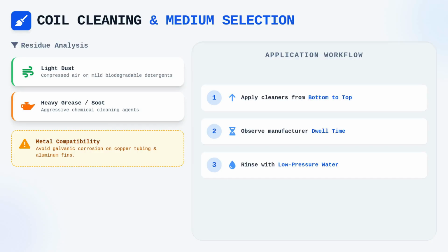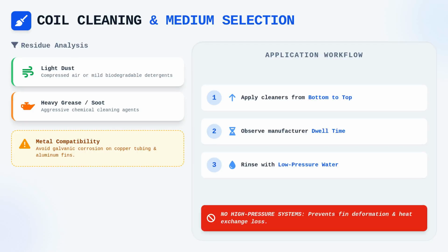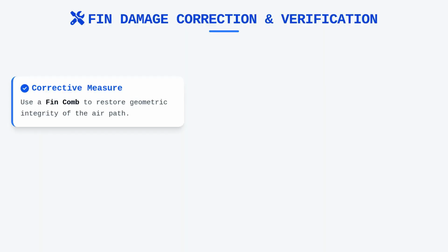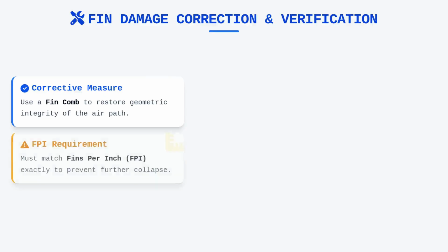Never utilize high-pressure systems indiscriminately, as they can easily deform delicate fins, thereby permanently altering the aerodynamic profile and reducing the heat exchange capacity of the unit. If fin damage has already occurred, the use of a fin comb is the only corrective measure to restore the geometric integrity of the air path. Each fin comb is sized by the number of fins per inch, or FPI, and must match the equipment specification exactly to be effective without causing further collapse.